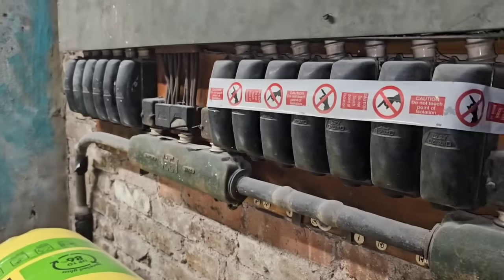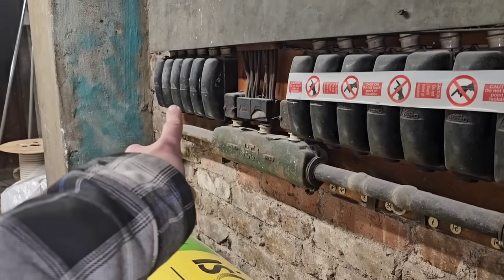So now they're replacing the central boiler system as part of the works, but it wasn't until it kept breaking down — like every week there'd be a call-out with ongoing maintenance issues. They thought all-electric would be the solution, but if you put in immersion heaters and storage heaters, these fuses are soon going to run out of juice. This system is just so antiquated the DNO really does need to upgrade it.